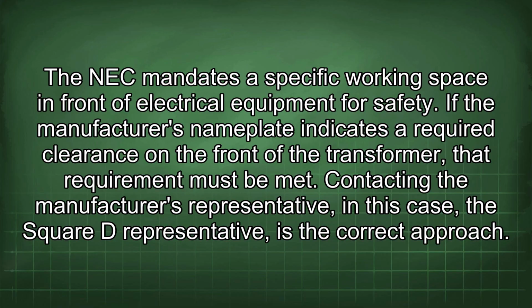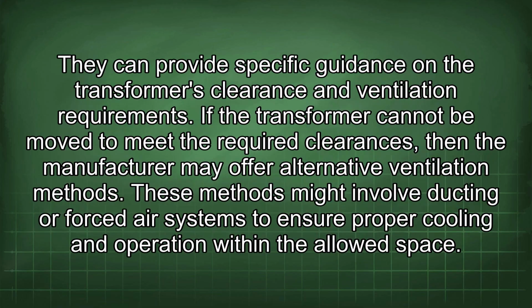Contacting the manufacturer's representative, in this case, the Square D representative, is the correct approach. They can provide specific guidance on the transformer's clearance and ventilation requirements. If the transformer cannot be moved to meet the required clearances, then the manufacturer may offer alternative ventilation methods. These methods might involve ducting or forced air systems to ensure proper cooling and operation within the allowed space.